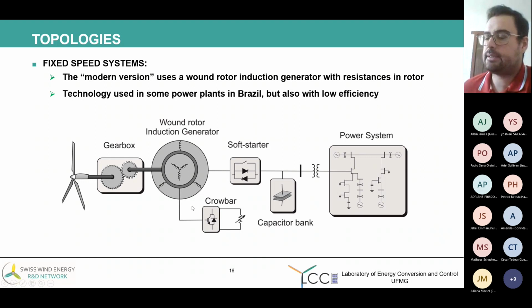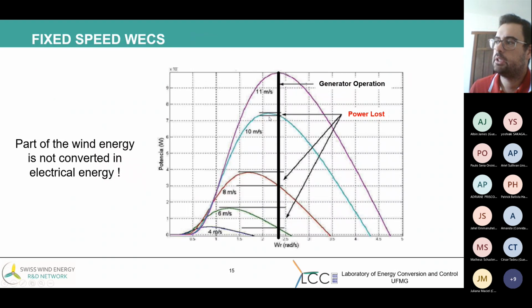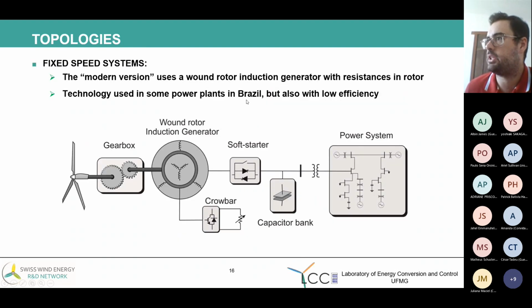The difference between this and the previous one is, as we have a wound rotor, we have variable resistance in this rotor that permits a wider variation of speed. But this variation is not enough to reach the maximum point. Because of this, I classify this technology as fixed also. This technology is used in some power plants in Brazil, but also has low efficiency. Also, I have seen some studies for offshore applications, but this is worse than the previous one.